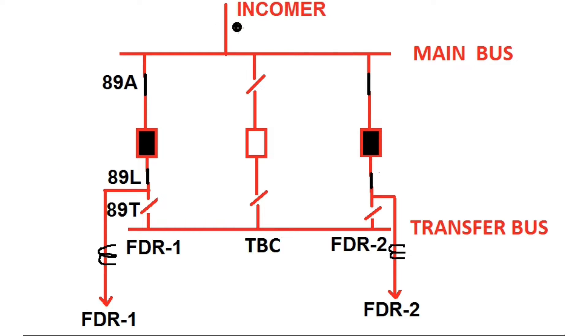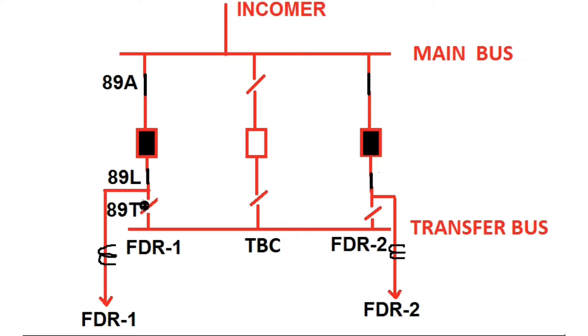This is the incomer circuit — it may be a transformer side, that is the LV side of any transformer, or it may be any feeder circuit. Through this incomer, the main bus is taking power. 89A is the bus side isolator, 89L is the line side isolator, and 89T is the transfer bus side isolator since it is connected towards the transfer bus.